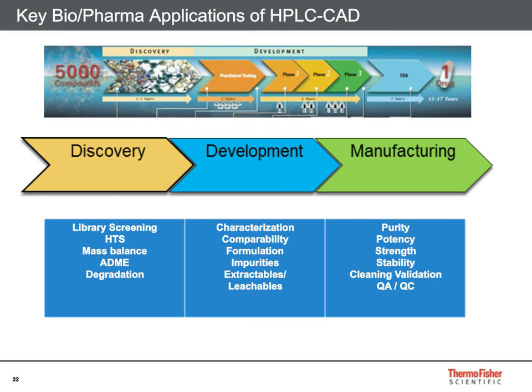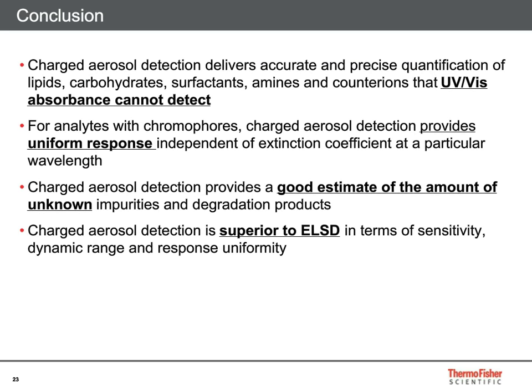Let's summarize what we've seen in the first portion of today's webinar. First, charged aerosol detection delivers accurate and precise quantification of lipids, carbohydrates, surfactants, amines, and counter-ions that UV-Vis absorbance cannot detect. Second, for analytes with chromophores, charged aerosol detection provides uniform response independent of extinction coefficient. Third, charged aerosol detection provides a good estimate of unknown impurities and degradation products even when no pure standard is available. And finally, charged aerosol detection is typically superior to ELSD in terms of sensitivity, dynamic range, and response uniformity. Now we'll proceed to Part 2 with Dr. Bruce Bailey.